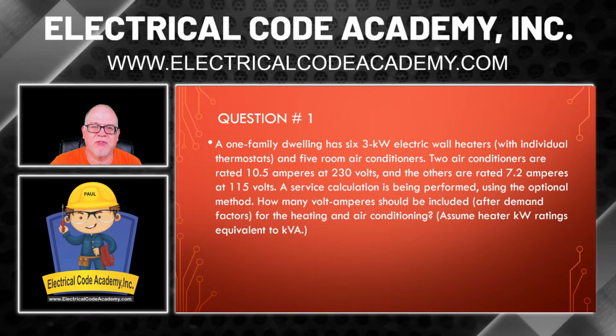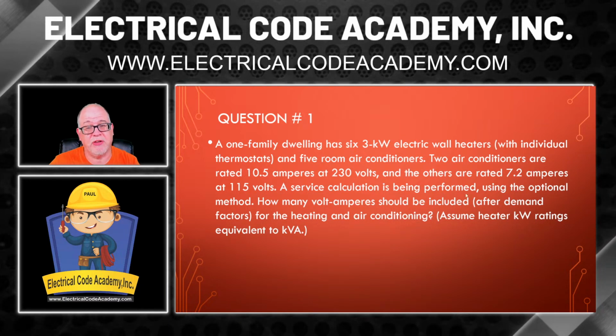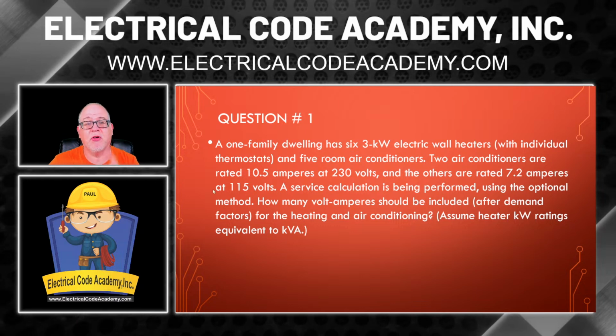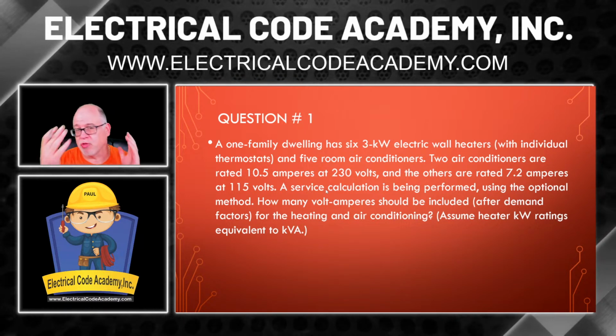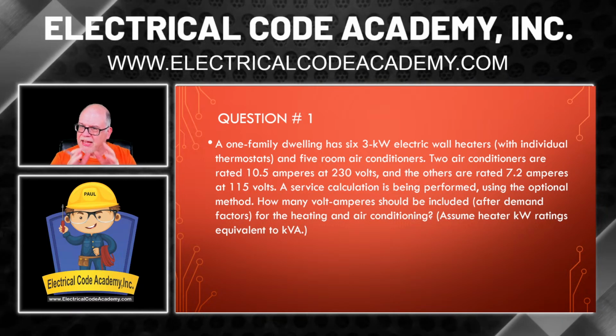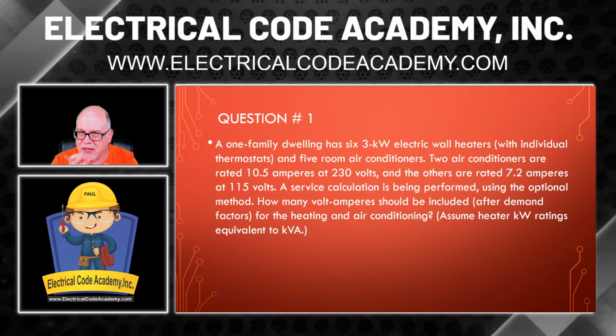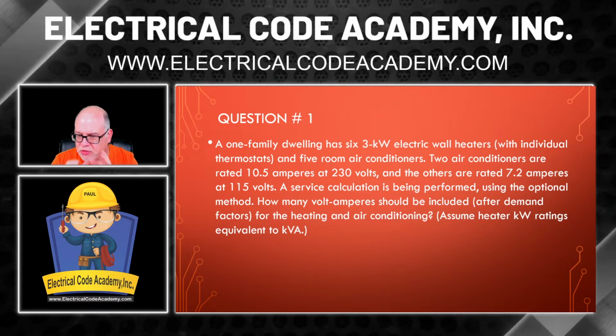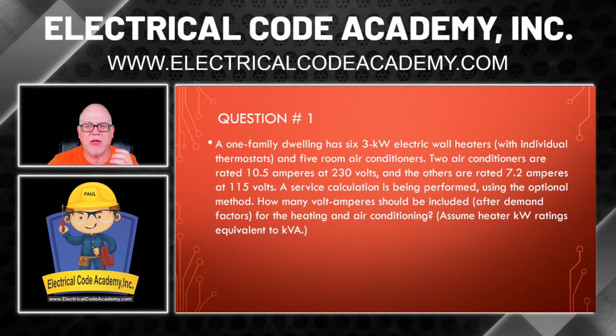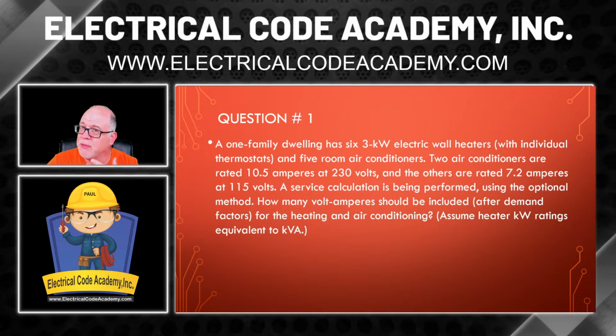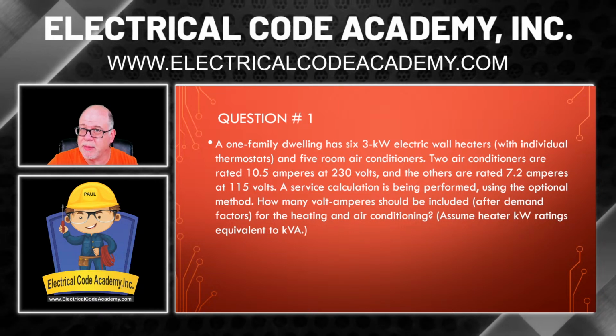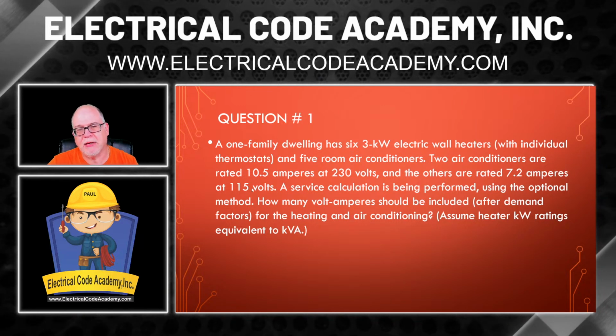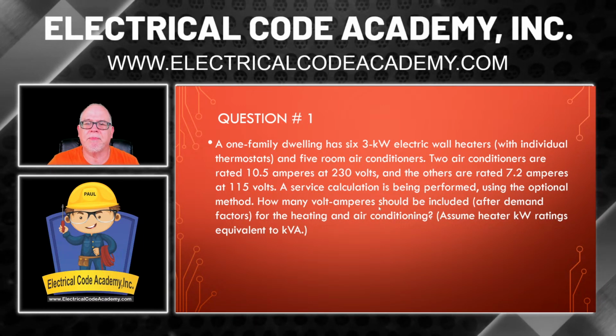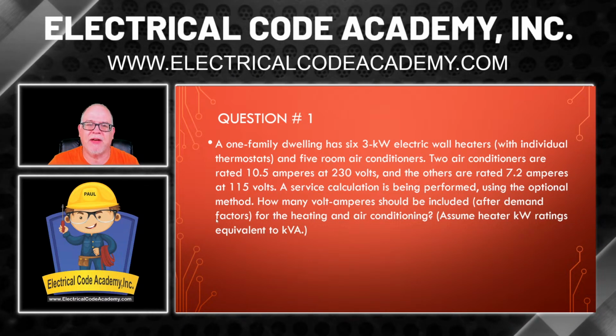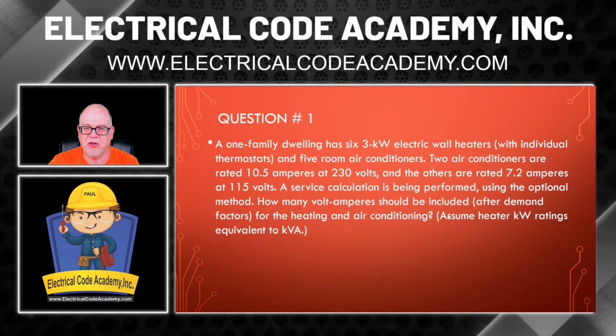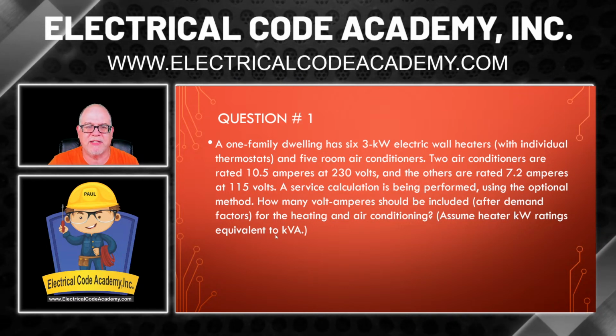All right, now it goes on to say, a service calculation is being performed using the optional method. So they'll be using the optional method to do their overall service calc. But it seems like we're only being asked to do the AC and the heat and compare the two. That's all we're being asked to look at right now. But it is reminding you that they're using the optional method, so that's going to put you in the optional area, which would be part 4 of 220, right? Okay, it says: how many volt amperes should be included after demand factors for the heating and air conditioning? Assume heater kW ratings are equivalent to kVA.